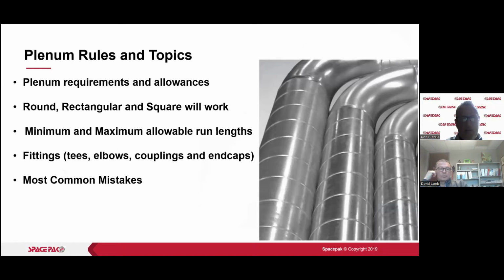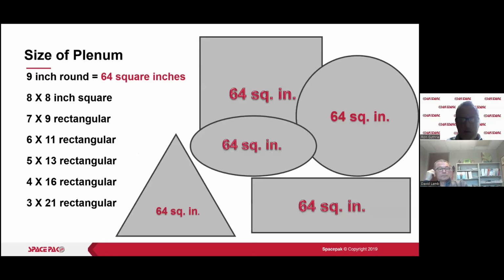All right, plenum requirements and allowances. We're going to talk about all those different things. We need 64 square inches. That can be 9-inch round, 8x8 square, 6x11 rectangular. It can be 3x21, but you better brace that because it'll be tin canning when the pressure builds up in it. Anything with 64 square inches, even a triangular duct, will work.